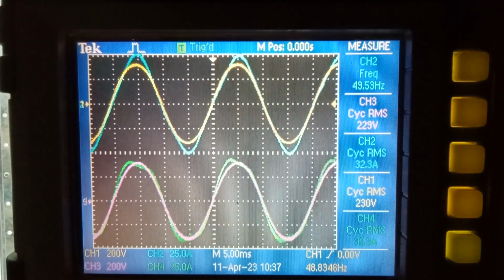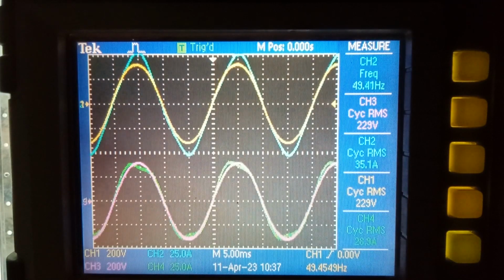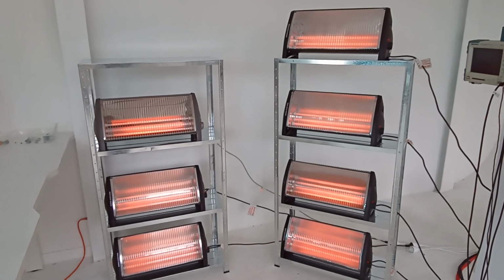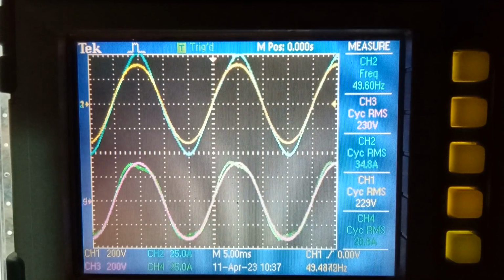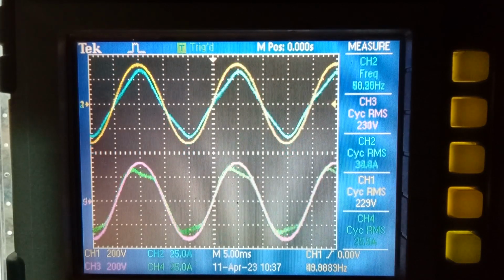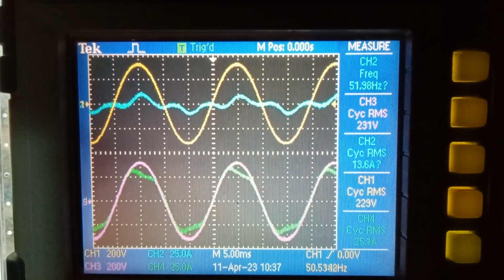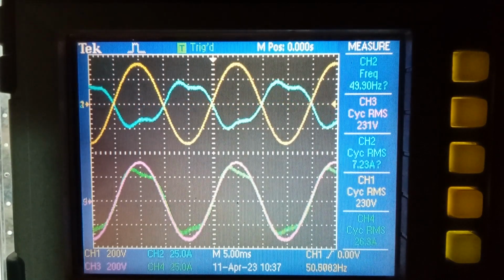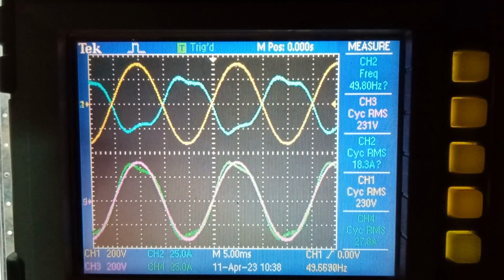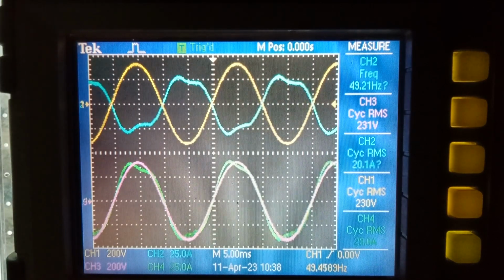12 kilowatts, plus the original 2 kilowatts makes 14 kilowatts we're supplying, with about 7 coming from the generator and another 7 from the inverter. And if we turn those off, you'll see that the inverter will supply less current and eventually its current will reverse and it will start charging the batteries. We're now going to turn the generator off and the system will transition to inverter only.